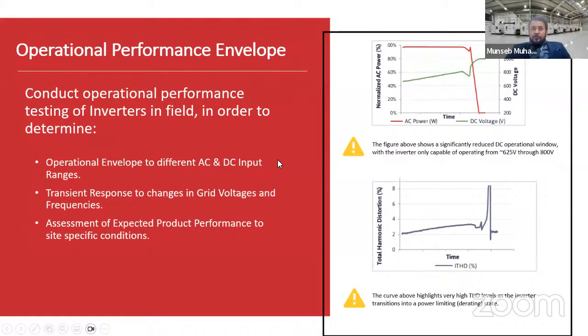So then we go to the operational performance envelope. That kind of testing is done in the field in order to determine the operational envelope to different AC and DC input ranges, for example, here in the graph on the top right. And then you do the transient response to the changes in the grid voltages and frequencies. And you do the assessment of the expected product performance to the site-specific conditions.